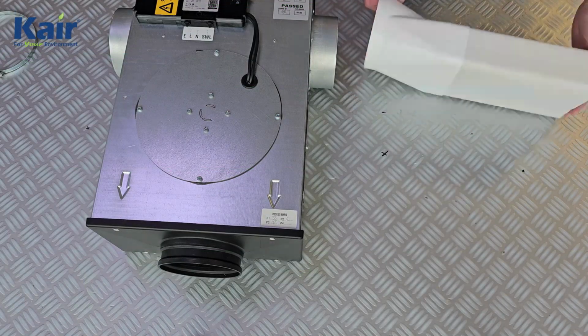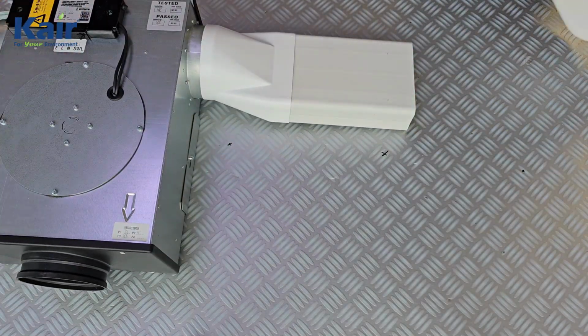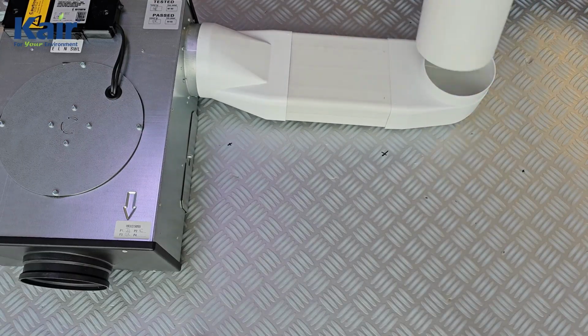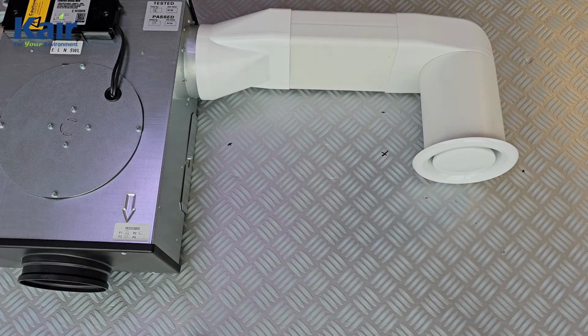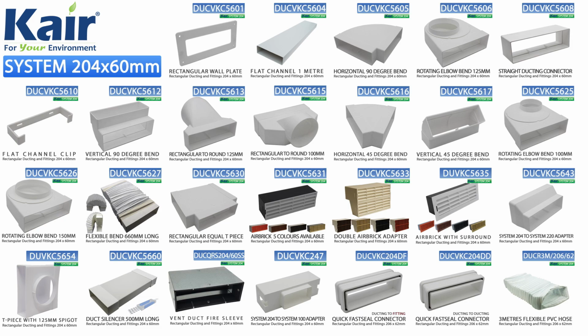When round ducting cannot be installed due to space restrictions, it can be converted to flat channel ducting using a round to rectangular adapter. The most common flat channel system for 125mm ventilation is 204x60mm.